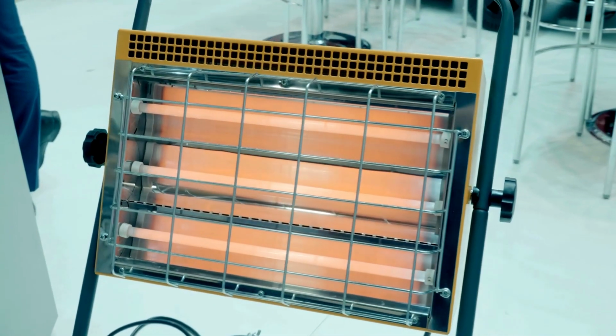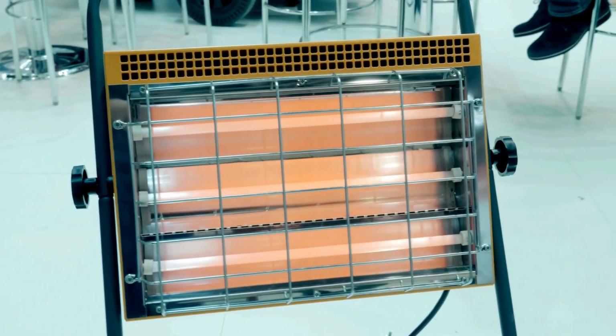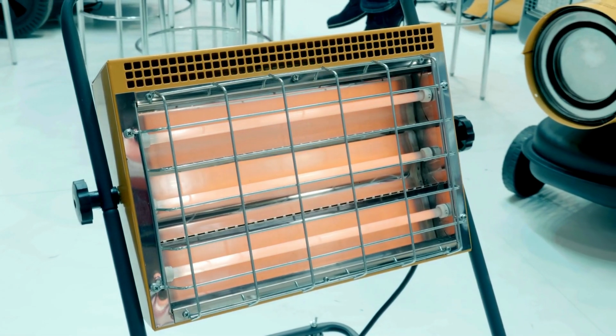Temporary heating equipment should be in good condition. If electric, it should have tip-over automatic shut-off and overheat cutoffs. Heating equipment with exposed heating elements should not be used.